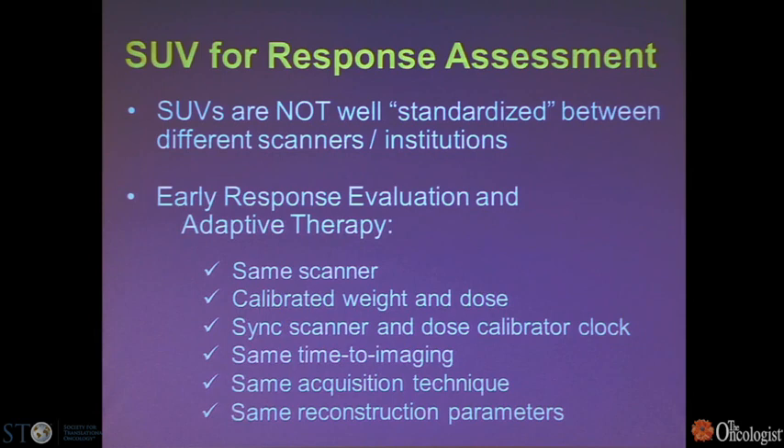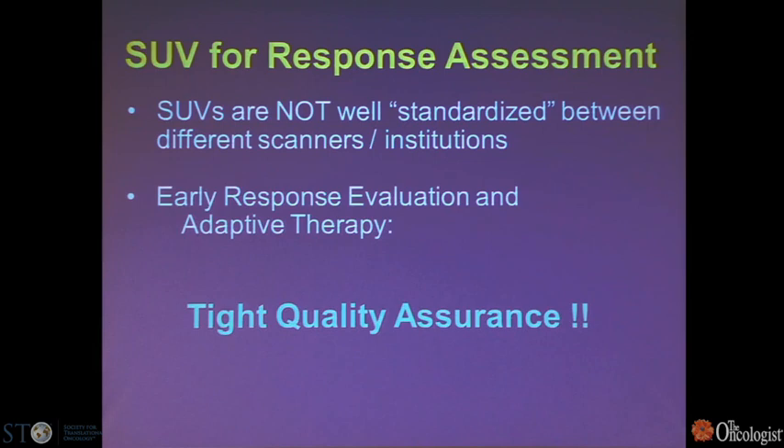When moving from single-institution to multi-institutional studies looking at response with PET, quality control is very important. SUVs really aren't standardized across different scanners, and a lot of attention to detail is needed. Ideally, use the same scanner; be careful with parameters like patient weight and dose; synchronize the clocks of the scanner and dose calibrator; maintain the same imaging time and acquisition parameters. Tight quality assurance is essential for multi-institutional trials, and the CALGB has provided that with core labs.